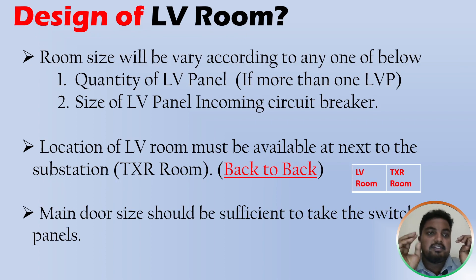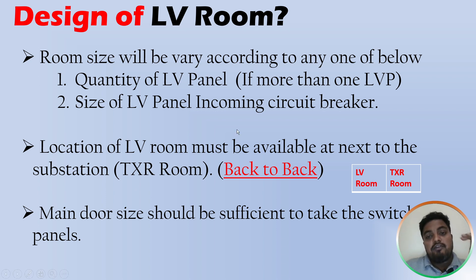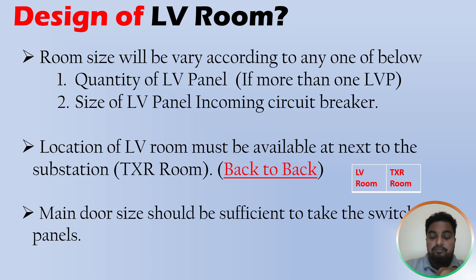The first thing in the design of the LV room is the size of the room. The size will vary based on two options. First, the quantity of LV panels — if more than one LV panel is in the LV room, the size will increase. If you have only one panel, the size mainly depends on the incoming circuit breaker of the LV panel. For example, a 2500A ACB incoming will require size X, while a 1000A ACB will require a smaller size Y.